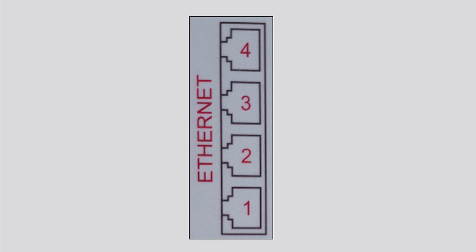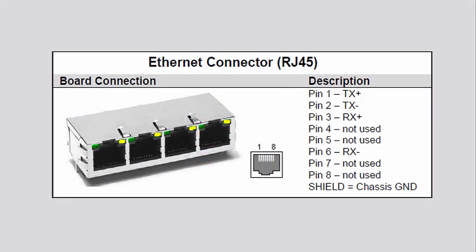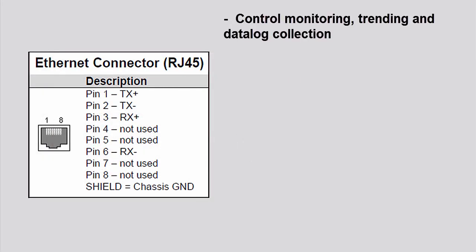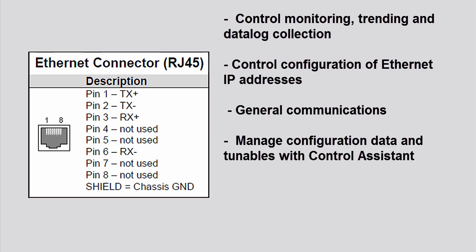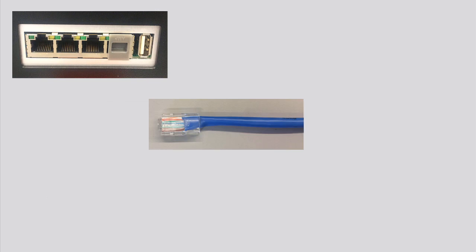The first available communication type is Ethernet. There are four isolated RJ45 Ethernet ports. The Ethernet connections can be used for multiple purposes with the controller, including control monitoring, trending, and data log collection, control configuration of Ethernet IP addresses, general communications such as Modbus, manage configuration data and tunables with Control Assistant, and 505 remote view connection. Connecting to the Ethernet ports is as simple as plugging an RJ45 Ethernet cable into an available Ethernet port on the back right side of the unit.